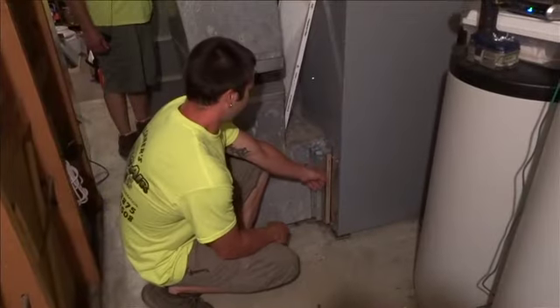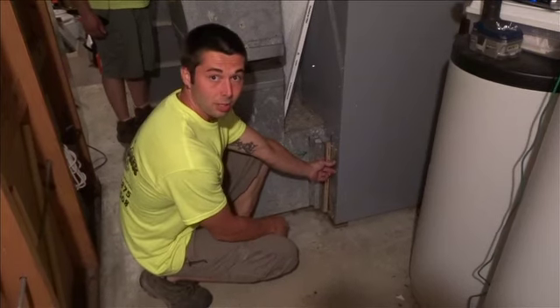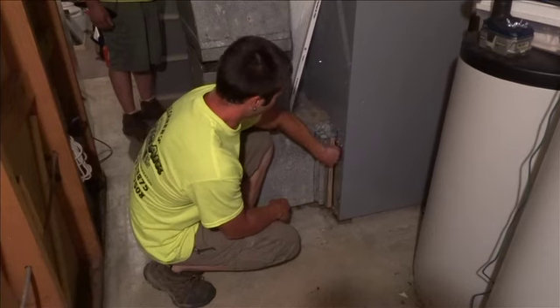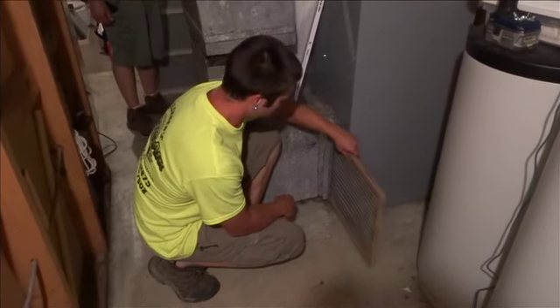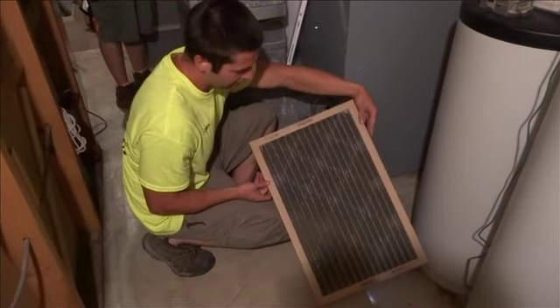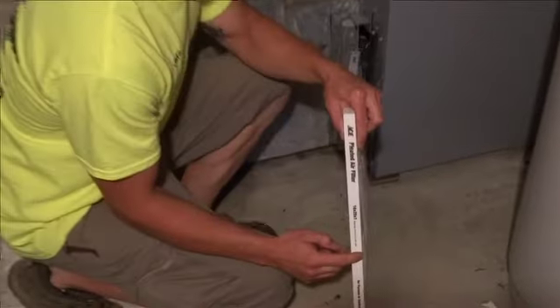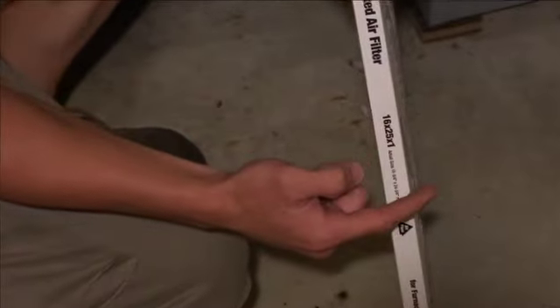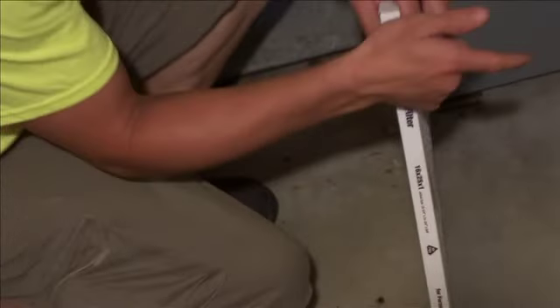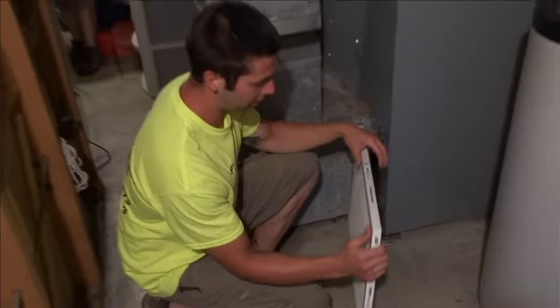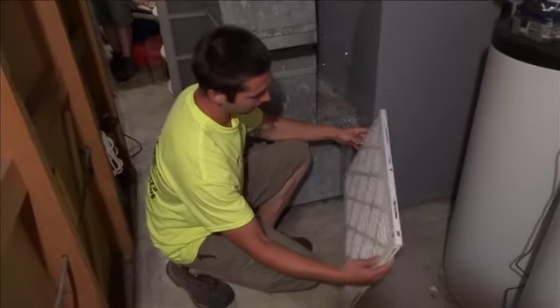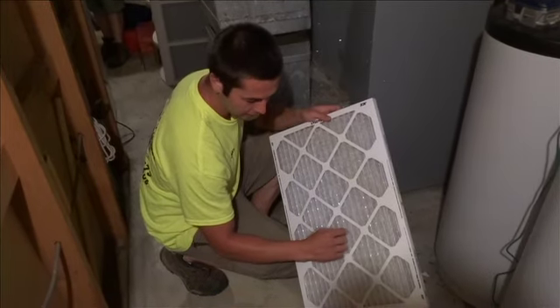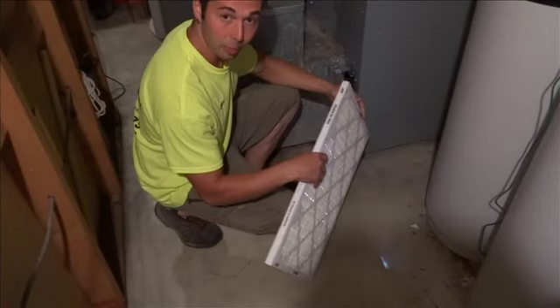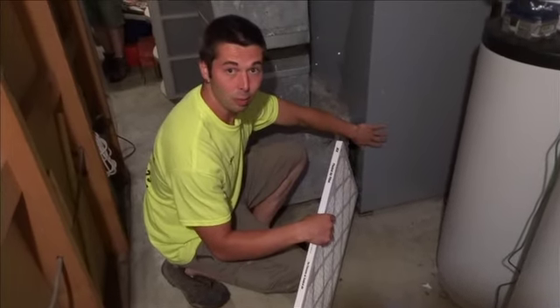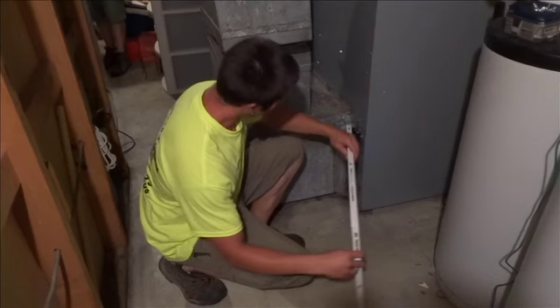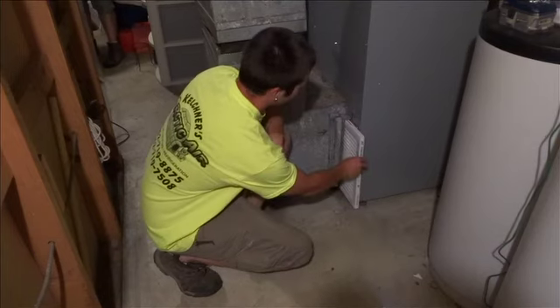The first thing we do when we come down and check the inside, we always make sure the air filter's clean. So pull the air filter out. Obviously this one's pretty dirty, so we're going to replace that one. You always want to make sure you have your airflow arrows facing towards the furnace, because your air goes into your furnace and then blows up through your house. If you put your filter in the wrong way, you've got these little metal fins here that stop your filter, if it breaks down, from pulling into your blower wheel. So you want to keep that going in the right direction.